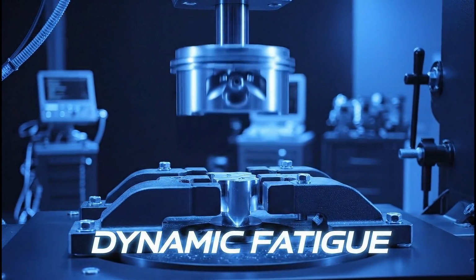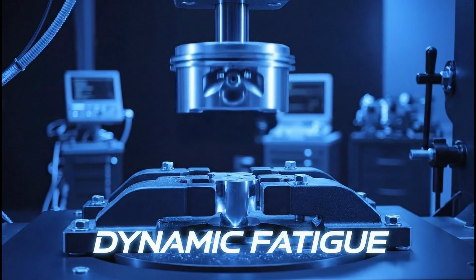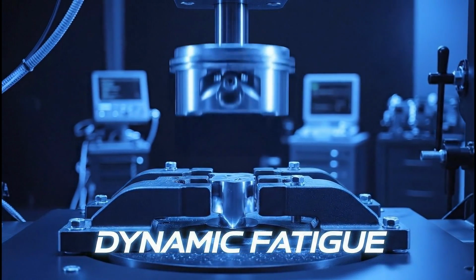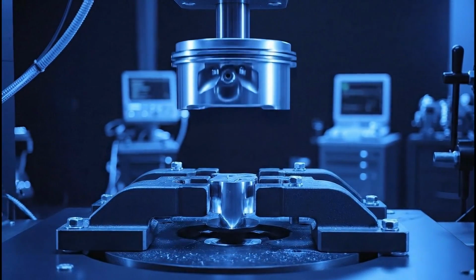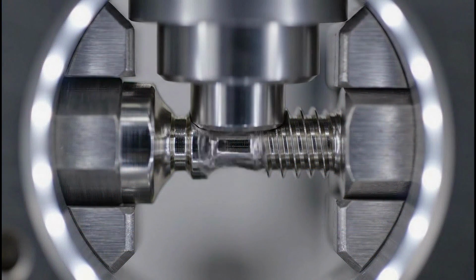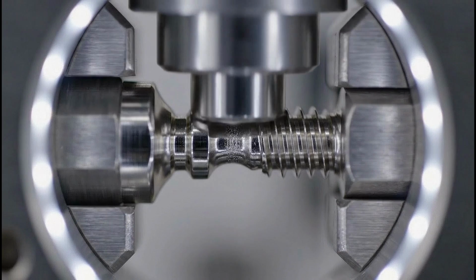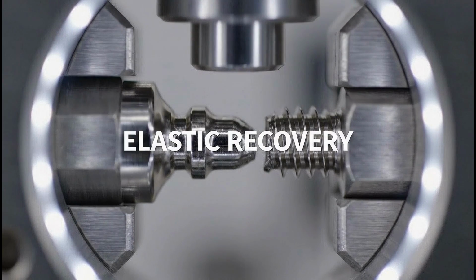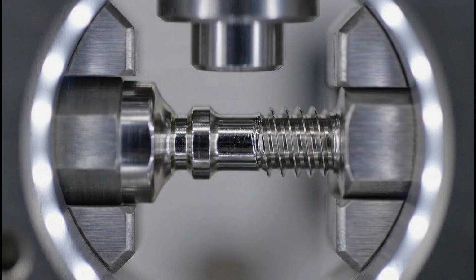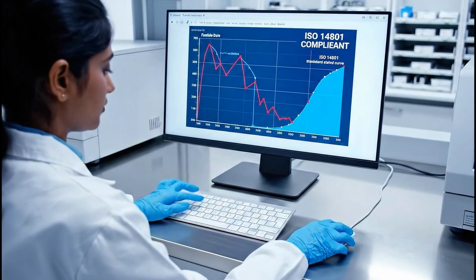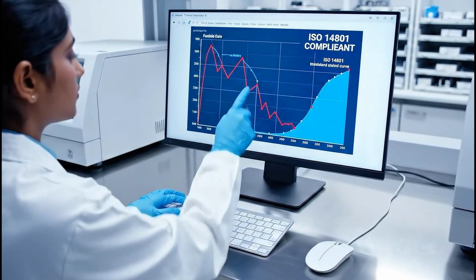Fatigue testing simulates years of chewing in just a few days. The implant undergoes millions of cycles. Titanium grade 5 has excellent elasticity. It absorbs the shock of chewing without fracturing. The results must exceed the ISO 14801 endurance limit. Our internal standards are even higher than the requirement.